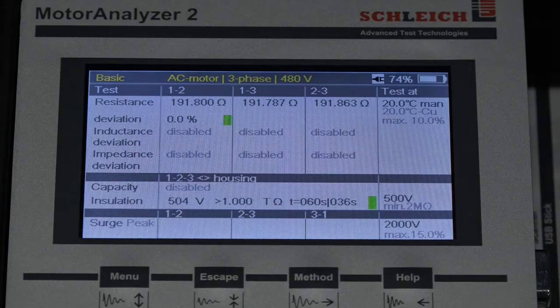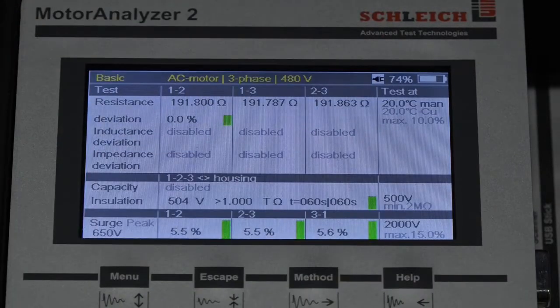This surge test takes a little bit of explaining, so while we're waiting for the megohm test to finish, I'll start. We'll start at 500 volts with the surge test and apply 3 pulses, one between leads 1 and 2, a second one between 2 and 3, and a third one between 3 and 1. And then we'll calculate the error area ratio on a pulse-to-pulse basis, or a peak-to-peak basis. And there we go. So we finished with our megohm test, started at 500, 525, on up. You can see it going up there. If we back up a little bit, we can see quite a bit of activity on those test leads.